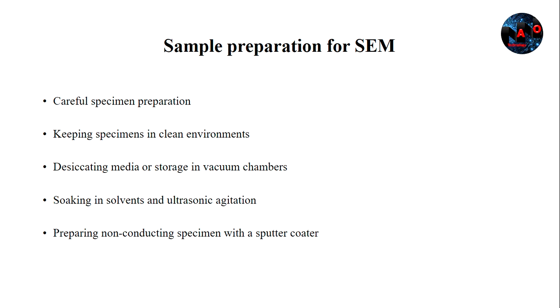By using argon gas and an electric field, gold is obtained. An electron from the argon is removed by the electric field, which gives rise to positively charged ions. The argon ions expel gold atoms which fall onto the specimen, covering it with a thin conductive coating.